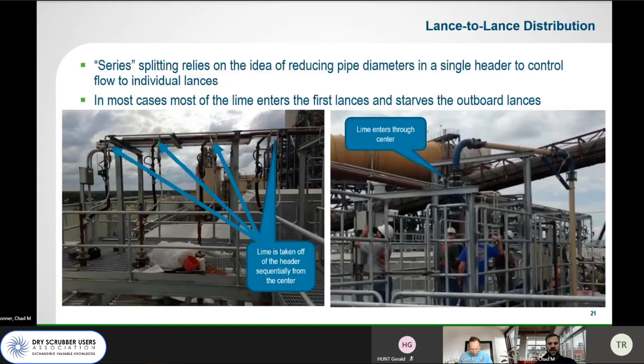So we started looking at lance to lance distribution. I simplified it into series splitting and parallel splitting. The system was originally designed with series splitting, where it relies on a common header with reducing pipe diameters to try and control the amount of flow to individual lances, where the hydrated lime enters through the center of that header and then gradually necks down on either end. But in most cases, the majority of the lime exits the header through the first or second lance, leaving the outboard lances starved of hydrated lime.